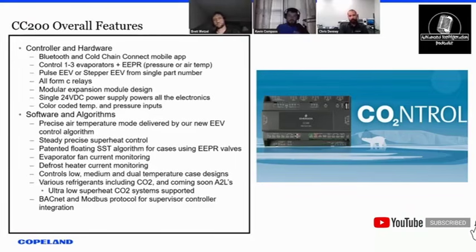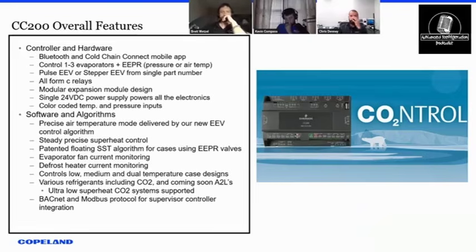Could you have a pulse valve on one output and a stepper on the other output? That's a good question. Right now, that's only supported if the scenario is pulse EEVs and stepper EEPR. Right now, we don't mix and match expansion valves. Currently, it's all pulse or all stepper on the EEV side. Does that not mean that you can't have pulsing EEVs with a bipolar EEPR? We can do that. That is supported. I have a chart that shows that coming up here. And the importance there, and you'll see it on the valve layout here in a moment, is if we do have a customer that wants to use EEPR, they can do pulse, expansion valve, and EEPR on the main controller all in one without purchasing any expanders.